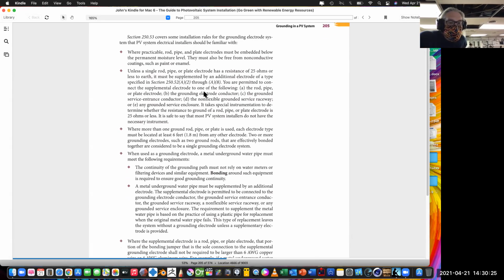All right. So I'll tell you, a lot of this stuff right here is just a lot of extra code stuff that isn't really that applicable. Now, you do have some issues of if you're going to connect to a pipe, don't do it. Don't do it. Just don't do it. That's all I'm going to say. I don't teach any other way. So if you take your ground wire and you don't attach it to a ground electrode that you put out in the ground yourself, you're asking for it. Because what people will do is say, well, I've got this pipe that goes to my well, and it's deep in the ground. Can't I use that for a ground electrode? Yeah, you can. But if you ever take that pipe off, you've completely ungrounded your system.